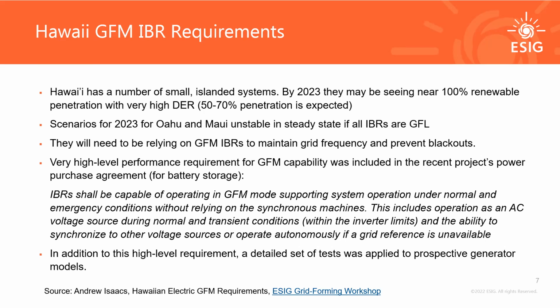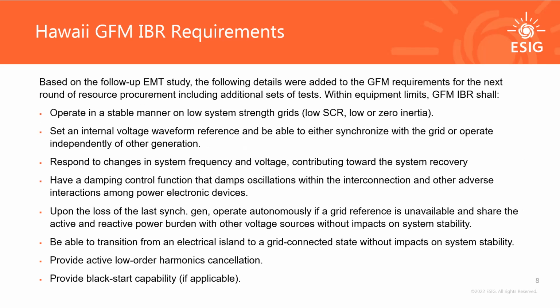So initially they came out with just a high level definition of what a grid forming inverter means and is supposed to do. I will not read it out, it's on the slide there. They said that every new storage resource or hybrid resource that will be procured has to comply with this definition. This is very high level. There are no specifications of functionalities. To clarify it more, a number of tests were applied to prospective generator models. Then a more detailed study was conducted on some of the Hawaii systems, and they came up with more detailed requirements for what grid forming is actually supposed to do, and came out with 8 functionalities.